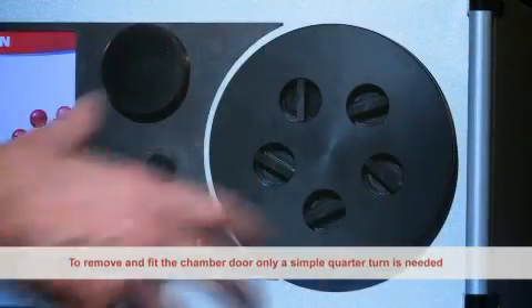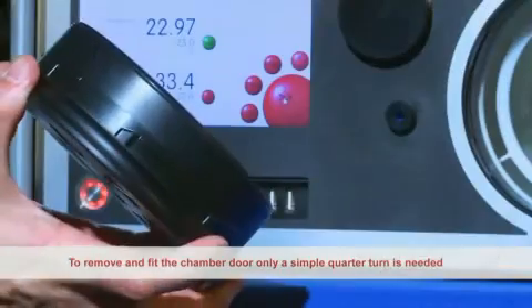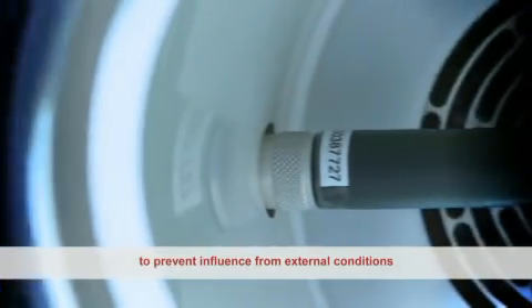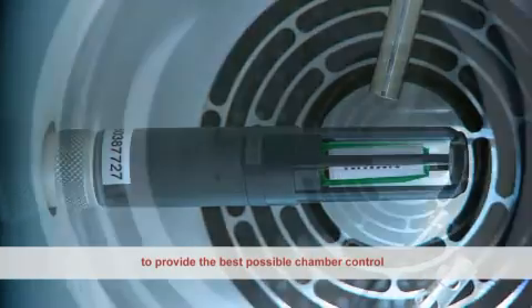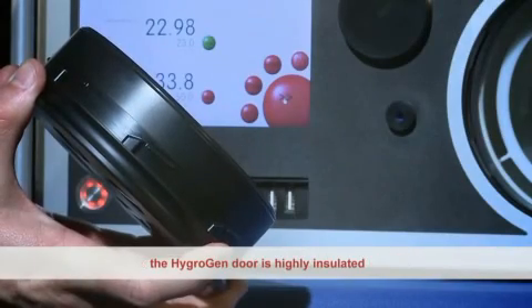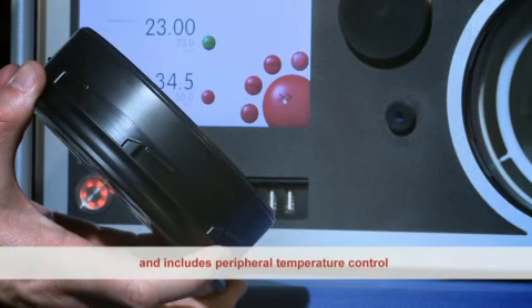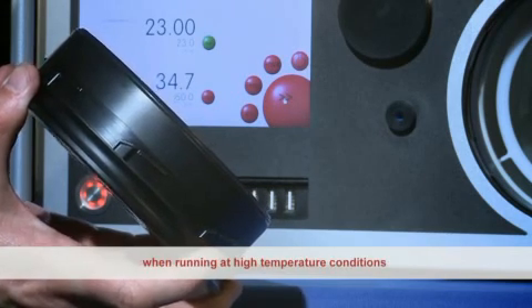To remove and fit the chamber door, only a simple quarter turn is needed. The test chamber is well insulated and sealed to prevent influence from external conditions. The HygroClip probe is carefully positioned to provide the best possible chamber control. To achieve temperature stability and gradient specifications, the HygroGen door is highly insulated and includes peripheral temperature control to reduce temperature gradients and condensation when running at high temperature conditions.